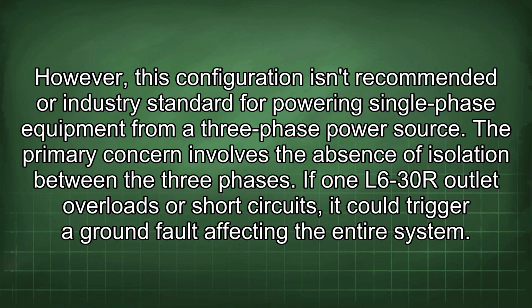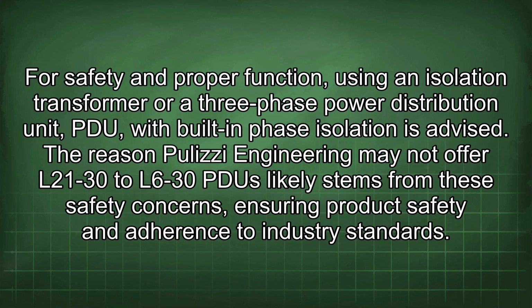source. The primary concern involves the absence of isolation between the three phases. If one L6-30R outlet overloads or short circuits, it could trigger a ground fault affecting the entire system. For safety and proper function, using an isolation transformer or a three-phase power distribution unit (PDU) with built-in phase isolation is advised. The reason Pulizzi Engineering may not offer L21-30 to L6-30 PDU likely stems from these safety concerns, ensuring product safety and adherence to industry standards.